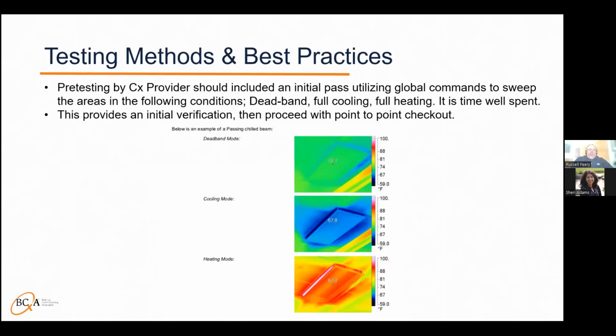Now, some testing methods and best practices. Pre-testing by a commissioning provider should include an initial pass using global commands to sweep the areas in the following conditions. So what we did is we walked through with the controls contractor and the general contractor and forced everything into a dead band. The building that we were doing was a 270,000 square foot, 5-story, and within a full day, we were able to walk through the entire building in all 3 modes of operation.